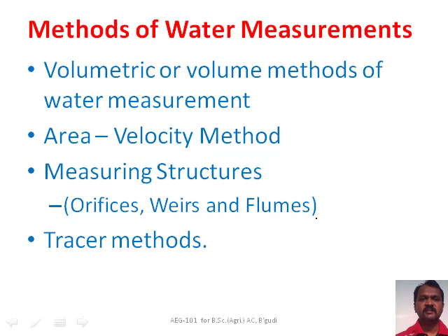First method, volumetric method. This method is used to measure small discharges flowing through a channel or pipe. This is a very simple and accurate method. When we are using this method for measurement of flow through a channel, some drop is necessary to allow the container to be placed at channel level for the collection of the discharge. Time to fill a known volume of container is noted with the help of a stopwatch. Here the discharge is equal to volume of water divided by time.